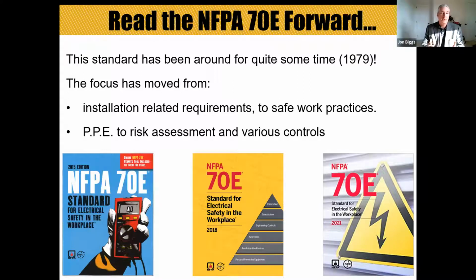The first thing to understand about NFPA 70E is it's been around for a long time, literally since 1979. The focus during that time has moved from installation related requirements, much like what we read in the National Electric Code, the NEC, to safe work practices. That focus has also transitioned from relying on PPE, as we did many years ago through the 80s and 90s, and even portions of the 2000s and the past decade, to now focusing our attention on risk assessment, really analyzing what it is we're doing, what risks are associated with those tasks, and what engineering and administrative controls can we use to eliminate, if possible, or at least minimize these hazards of shock, arc flash, and arc blast as much as possible.